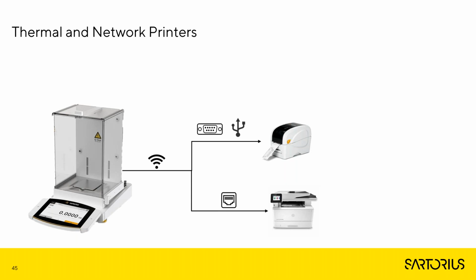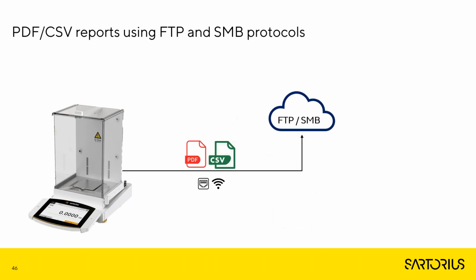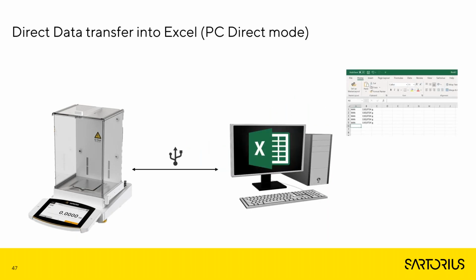Connecting the printer is very easy. You can connect the big office network printers over the Ethernet or wireless connection, or you can use the thermal printer using the USB or serial connection. Next slide. This is the option I mentioned in the previous slides, that the balance can generate reports in PDF and CSV formats and store them, for example, on the FTP server or on a network shared location using the SMB protocol. For that, you need the balance to be on the network. Next slide. We also have on Cubis II a so-called PC direct mode. That means you can transfer your results directly into Excel, which is installed on a computer connected with a USB cable to the balance. No middleware is required in this case. Next slide, please.